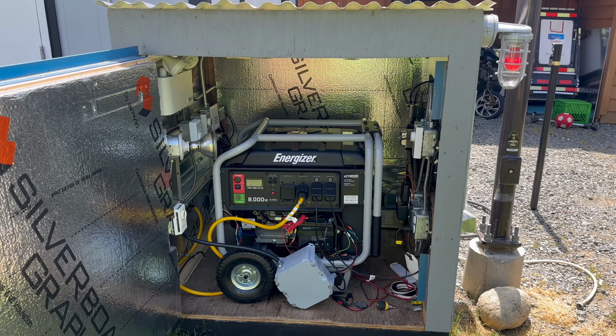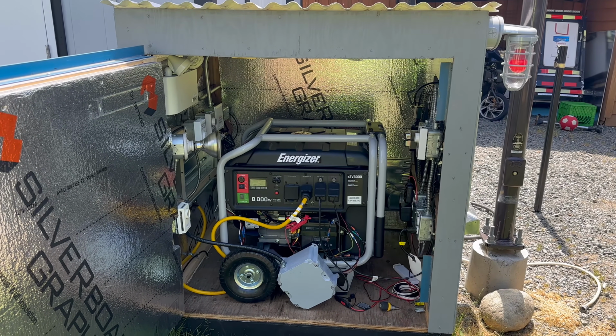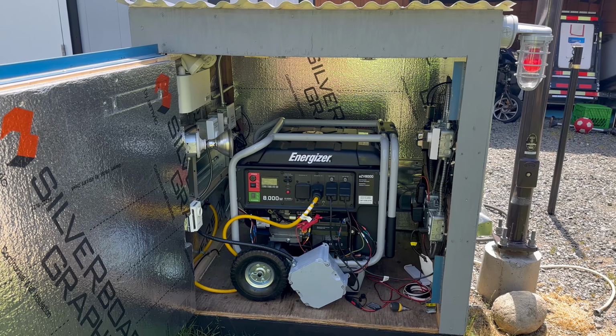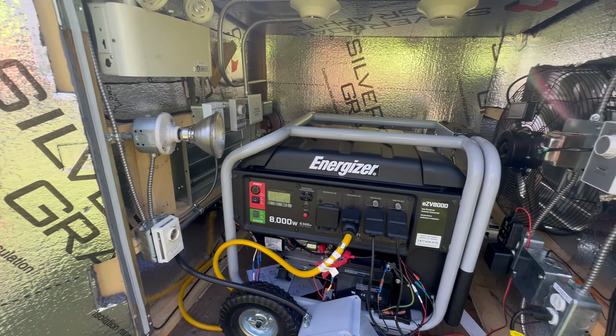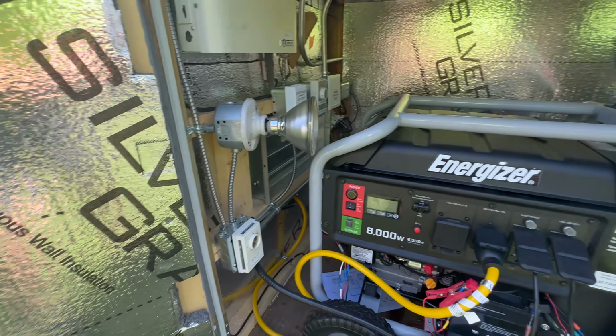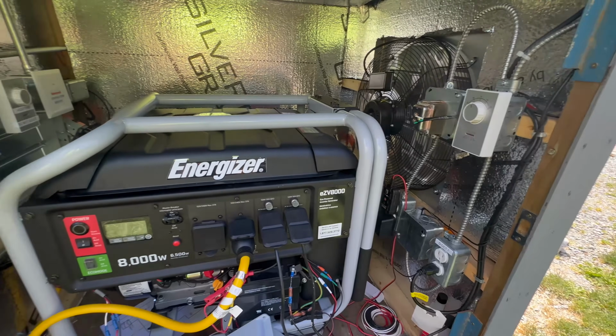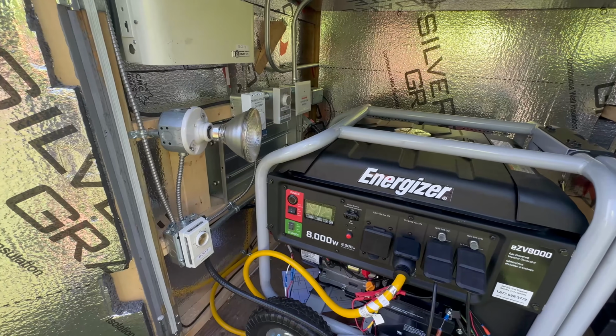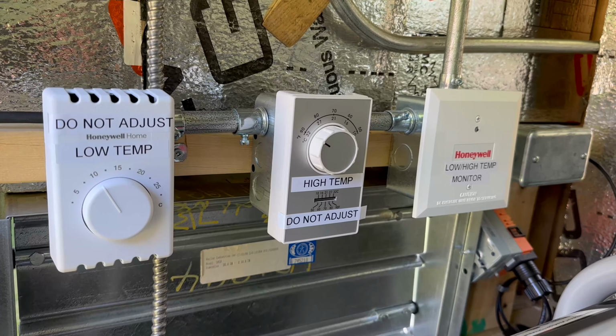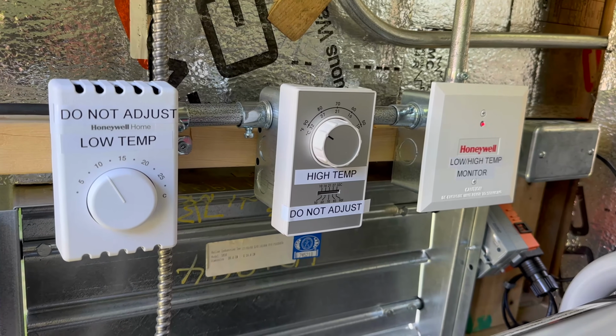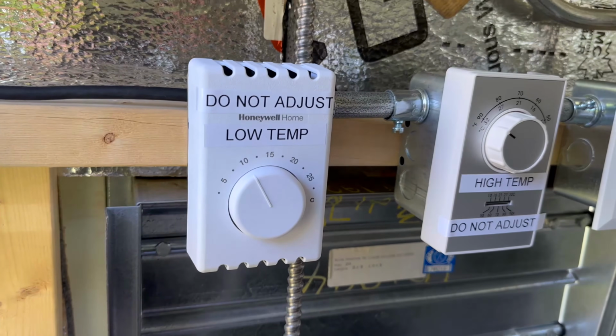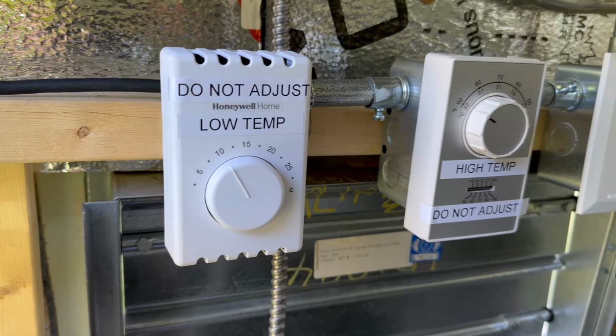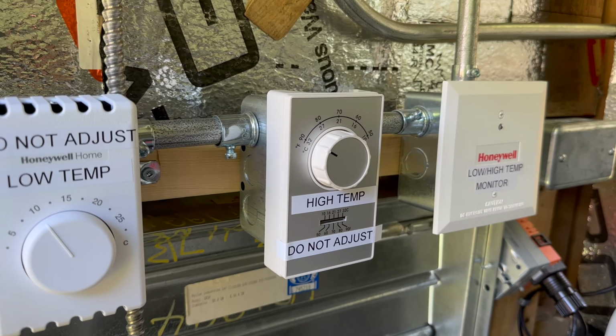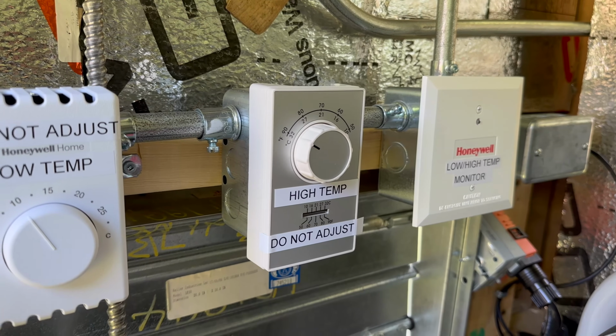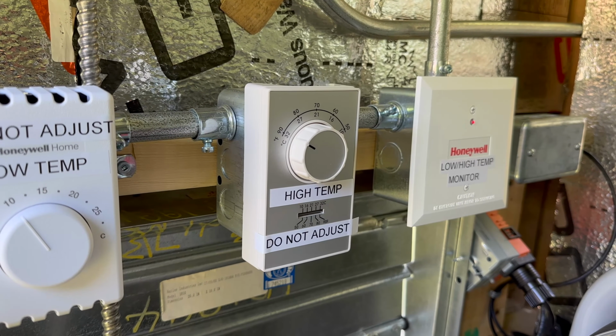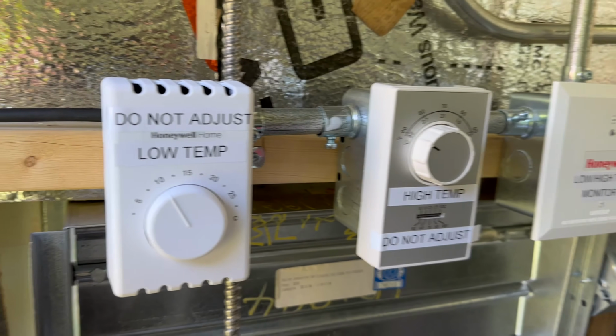That almost concludes the portion of this video about the ventilation system, though I want to show the redundancy that I have put in place in case something goes wrong. As this system provides automatic heating and automatic ventilation, there is also redundancy built in for both of those systems. That comes in the form of these alarms right here. These are just thermostats, the same that controls the heating and ventilation, where we have a regular heating thermostat for the low temperature and a reverse acting thermostat for the high temp alarm, which may sound counterintuitive, being the reverse acting cooling thermostat is actually the alarm for the high temp and vice versa.